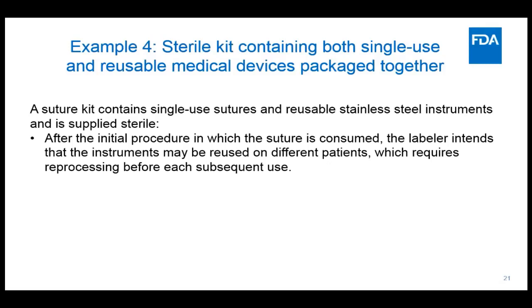It may contain 1 or 2 or 3 of these, and one of these 4 things and 2 of these things, based on the order of the healthcare professional. And that DI broadly covers the customization of the device. And like Loretta said, the production identifiers would be the way that you could trace it to: this is the one Dr. Jones ordered for patient A, and this is the one Dr. Smith ordered for patient B.